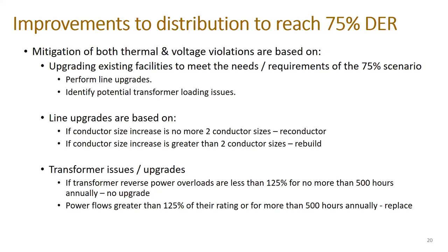For transformer upgrades, primarily substation transformer upgrades, because we didn't really look at the individual distribution transformers, because if they're serving load now, they should be able to serve load once the DER is in place. So we looked primarily at substation transformers to understand if there were reverse power flow overloads associated with them. And we kind of arbitrarily said that if the reverse power overloads are not more than 125% for any longer than 500 hours annually, most transformers can accommodate that. If, on the other hand, it's greater than 125% or the overloads are more than 500 hours annually, we're going to have to do some level of replacement. Next slide, please.